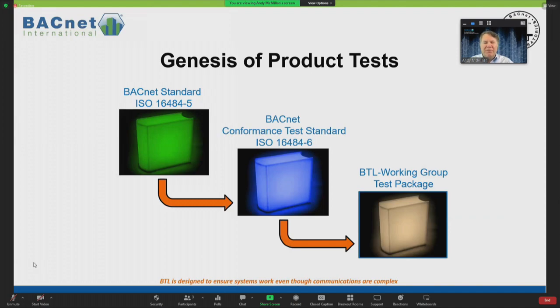The tests for BACnet are a companion standard. There's a standard for BACnet, and there's another standard right next to it, which is the test standard, and that's where the basic tests live. They're developed by the BACnet committee and by the BTL working group, which I'll talk about in a second. The BTL working group itself generates the test package, which is the formal set of documentation by which products are tested.